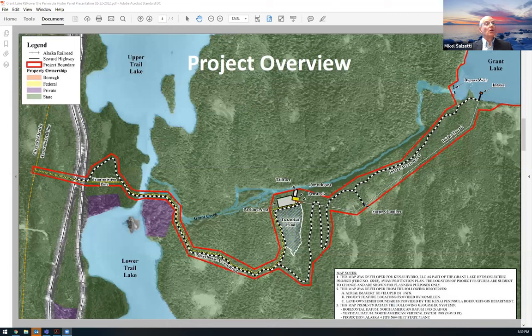So the project as a whole doesn't have a dam on it, really just a small bypass weir here, which controls the flow out of the lake into this bypass area to put in the required bypass flows. The water will go through an intake structure into a 10-foot horseshoe-style tunnel. It'll be about a 1% grade all the way down to this area here, where it'll transition to a 15% grade. The water will exit the tunnel at a rock face into a 6-foot steel penstock, where it runs down into the powerhouse and bifurcates into two 4-foot pipes that go into 2.5 megawatt Francis turbines.